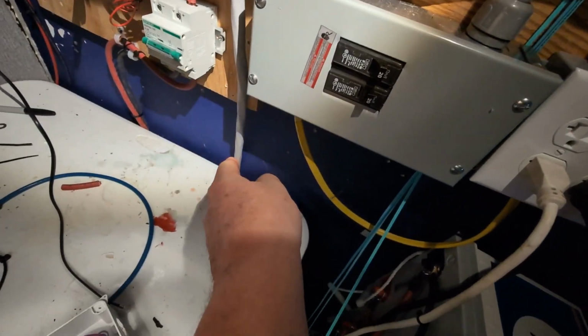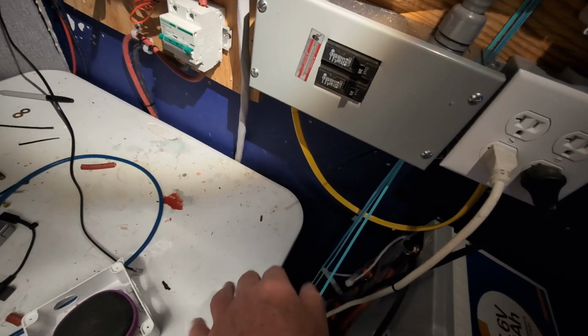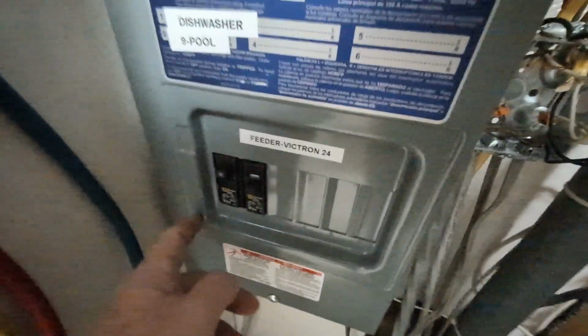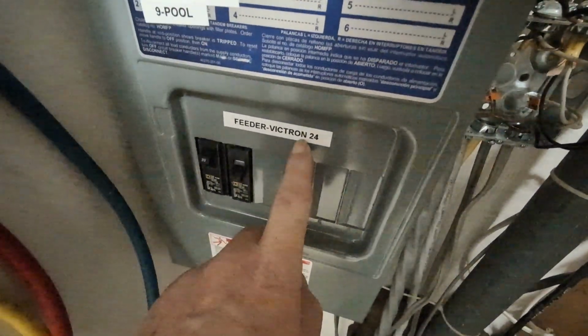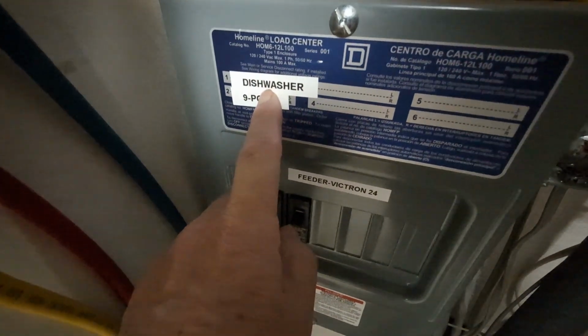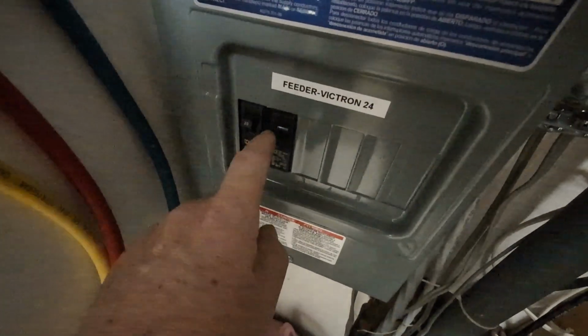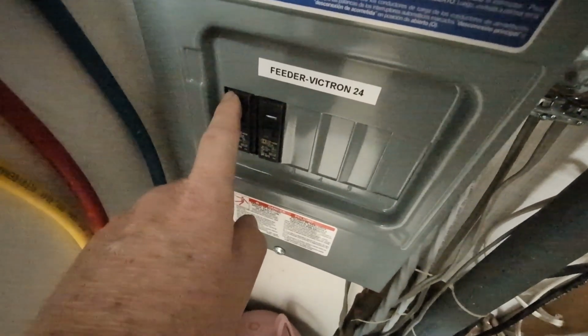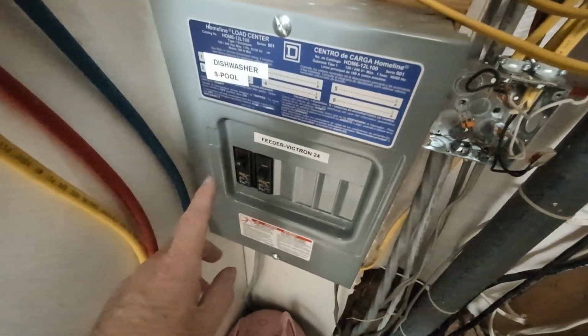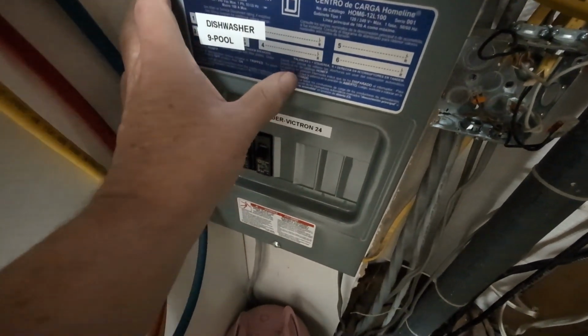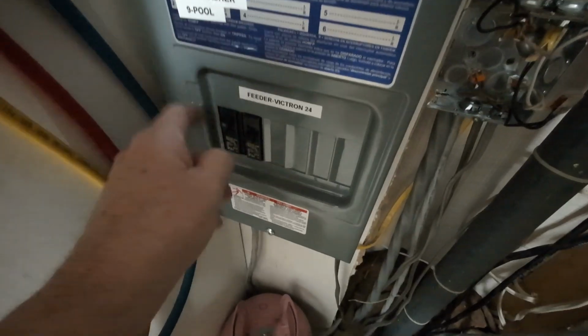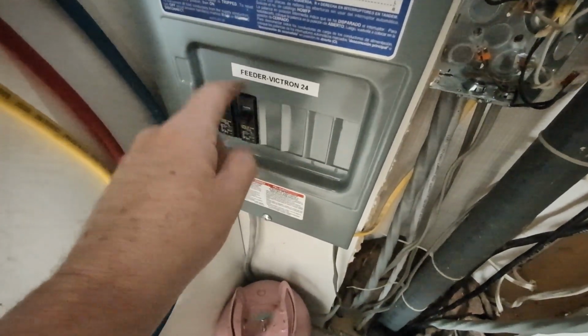And then that takes this from copper back to aluminum, and then that wire, that service entrance cable, the gray one, goes down under the house, and then through the miracle of science and this service entrance cable here, which is capable of handling about 50 amps at 240 volts, that feeds this panel, the feeder from the Victron 24 volt. And on this circuit I have 2 breakers, one for the dishwasher and one for the pool pump. And right now the pool pump is off and the dishwasher is on. So the power comes from that 24 volt inverter, solar power or grid, gets passed through from the Victron to this circuit panel and feeds the dishwasher and the pool circuit.